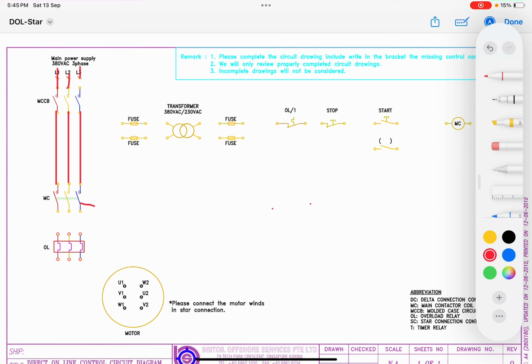So now at the magnetic contactor input, power supply is available. Since the magnetic contactor contacts are in open position, power supply cannot flow through the contactor. Once this magnetic contactor closes, power supply from your contactor will be available, and it will go to your OLR, which is your overload relay. And after the overload relay, it is going to go to the winding of your motor.